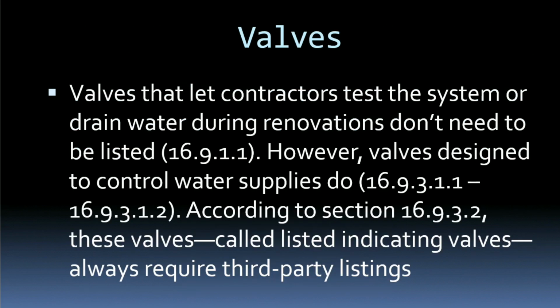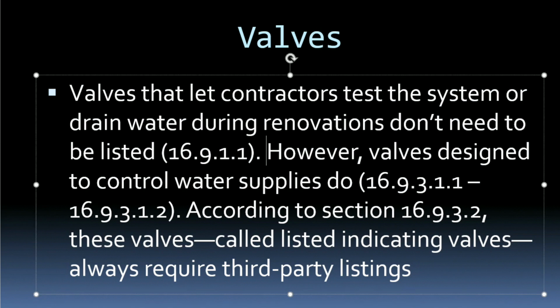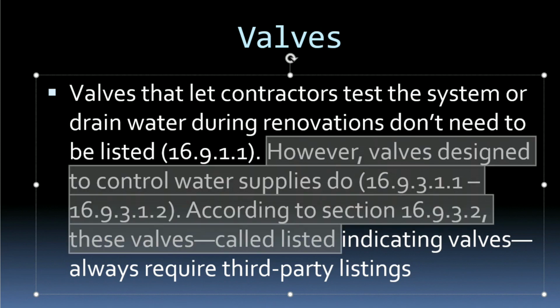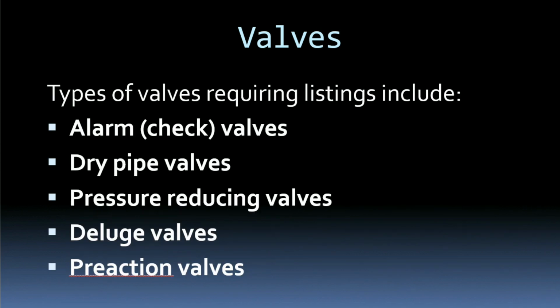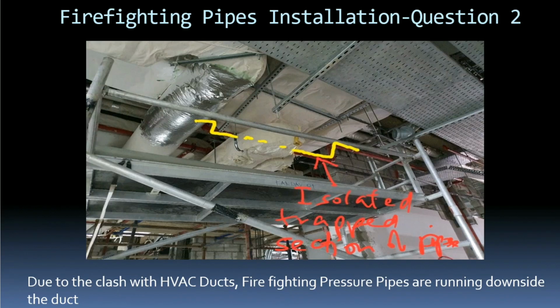The next one is the valve that lets the contractor test the system or drain the system; that need not be listed. However, a valve designed to control the water must be listed. So the control valves like the alarm check valve, dry pipe valve, pressure reducing valve, deluge valve, and preaction valve are the important valves that should have listing. Then coming to drain connections like the inspection test point connection and flushing connection, we don't need to have listing for these. And at the very starting I asked this question: the firefighting pipes are pressure pipes, so can we bend the pipes up and down like this arrangement or not?